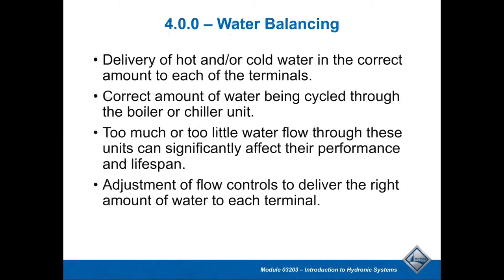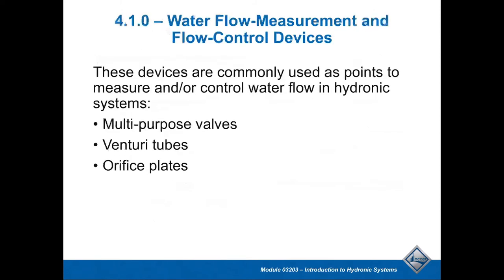For example, with a water chiller, you've got to move water through it, and there's a certain minimum — or really almost a design — flow rate. Sometimes there's a minimum, sometimes a maximum, but there's a range where they want that water flow. If you have too much water flow, that'll lead to excessive pressure drops in systems and could cause problems with valves and valve seats. We also want to make sure our terminal units have an appropriate amount of water — not too much, certainly not too little.